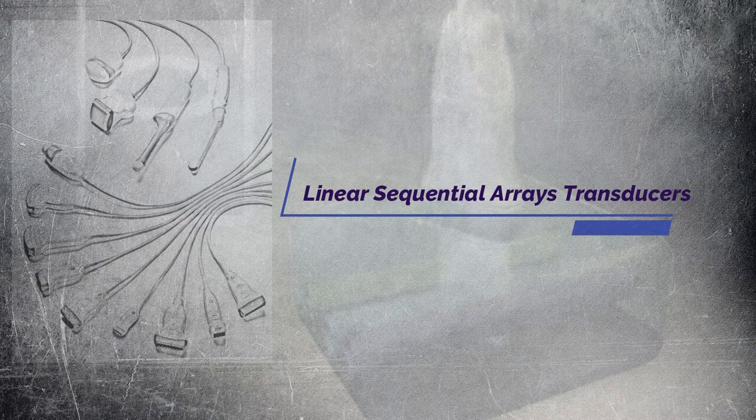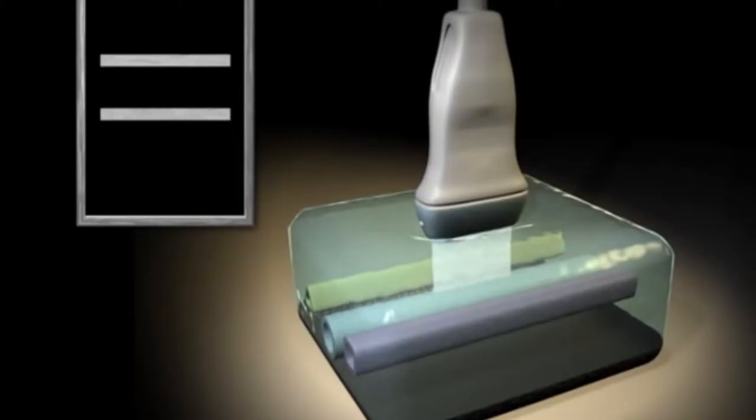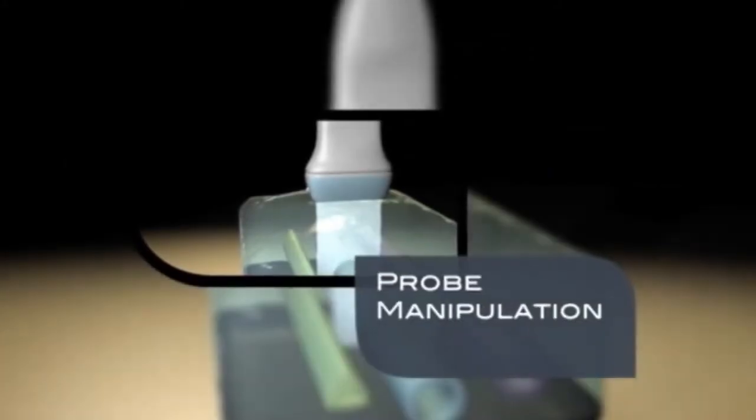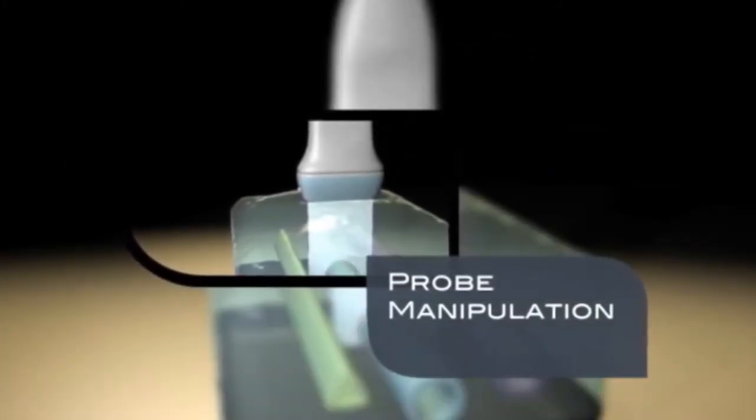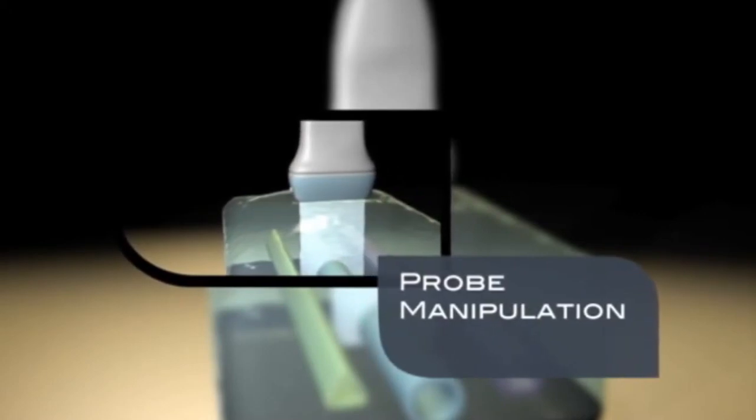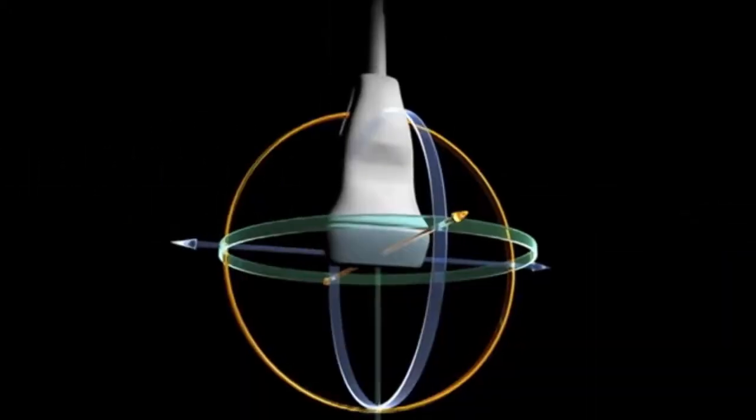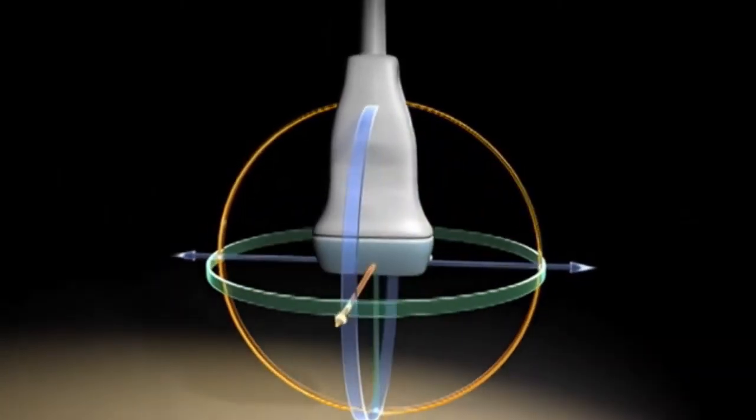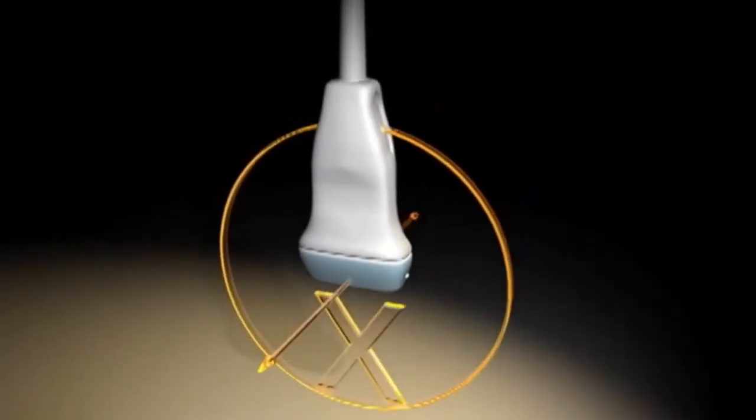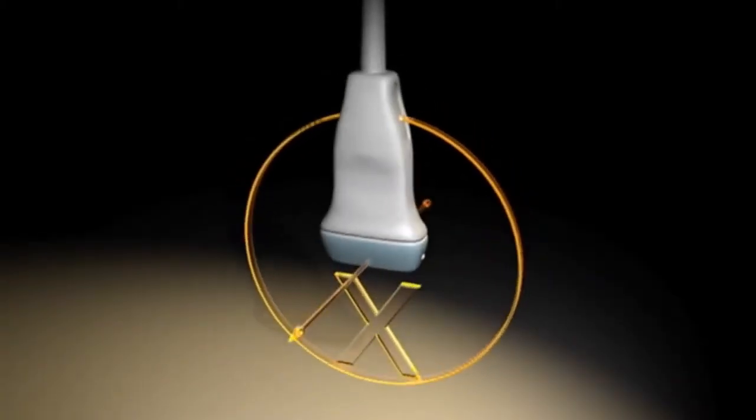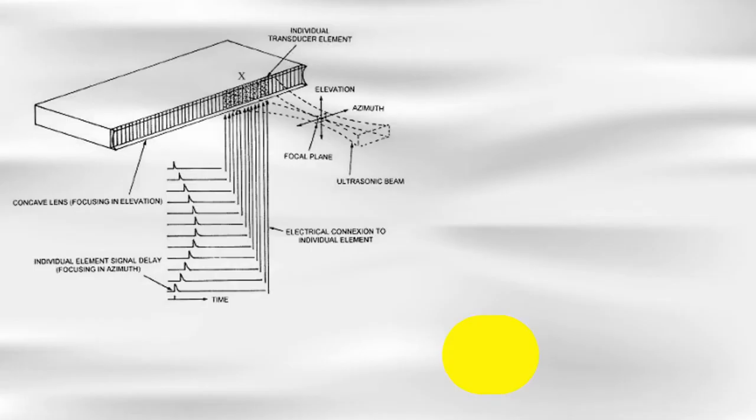Let's know about linear sequential arrays transducers. The scanning lines are directed perpendicular to the face of the transducer. The beam is focused but not steered. Linear array transducers are available with 512 elements in currently available ultrasound scanners. Generally, up to 128 elements are selected at a time for operation. As is obvious from the diagram, the field of view with a linear array arrangement is limited to the rectangular region directly in front of the transducer.